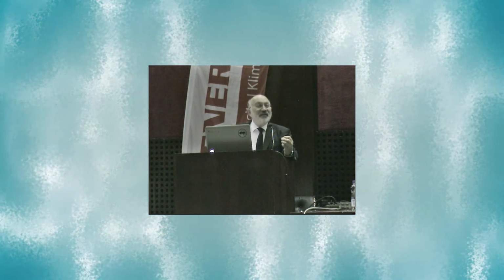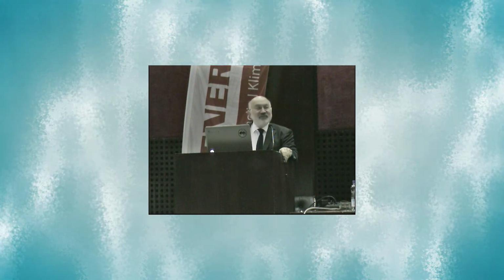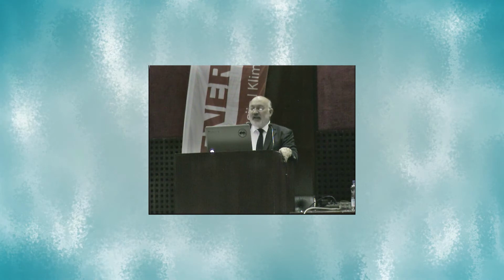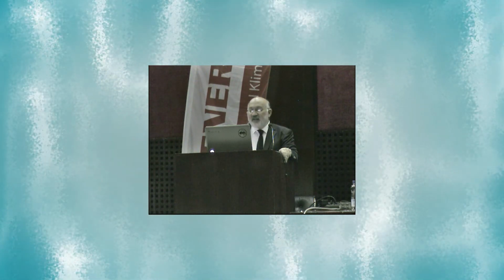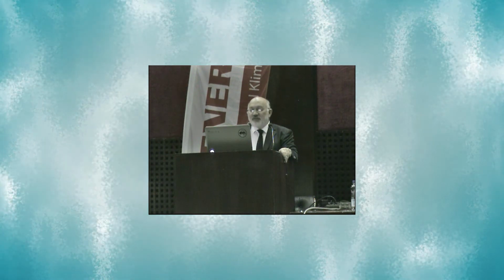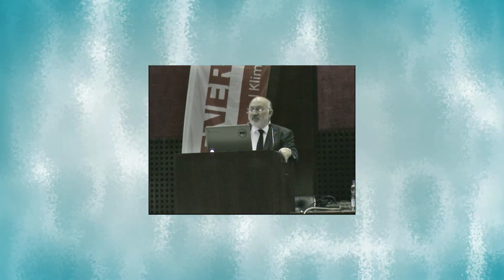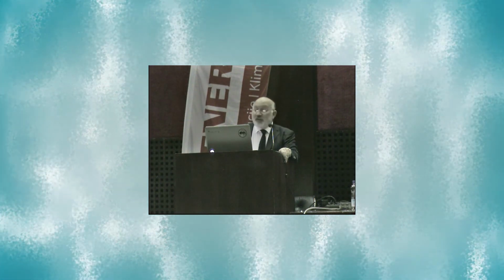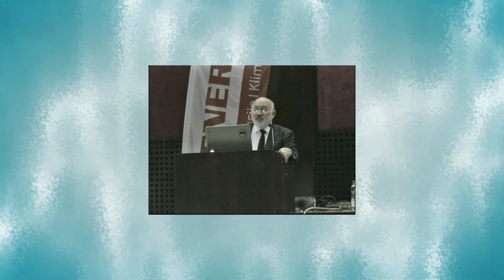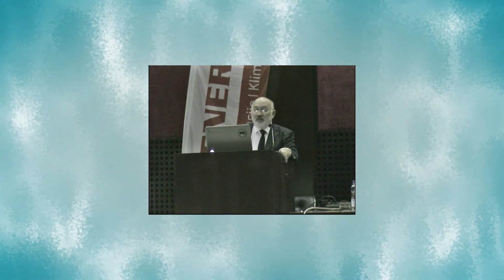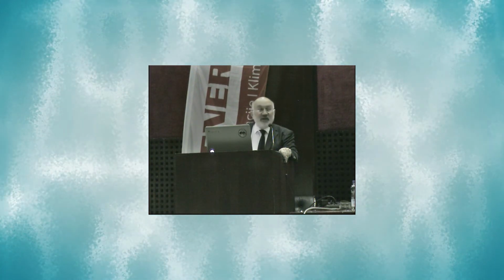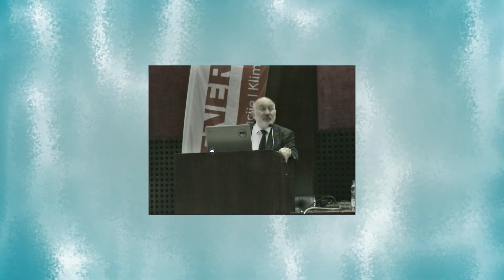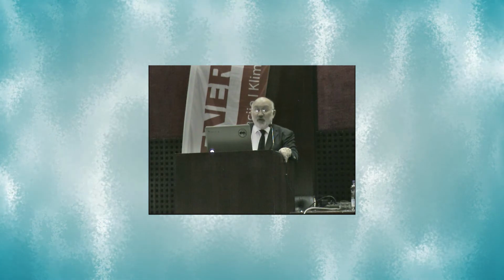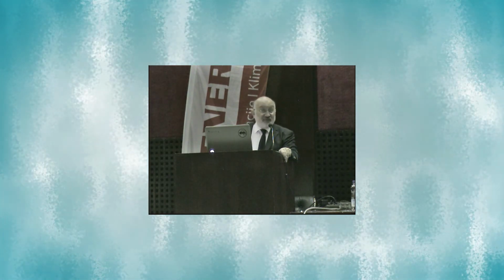Some results are shown here in a TS diagram, with R134A in blue and CO2 in green, for exactly the same conditions, shown by the dashed lines for air inlet and outlet from the condenser and evaporator. For CO2, the same size gas cooler or condenser brings the temperature much lower than the condensation temperature in the condenser. So instead of subcooling, we're able to bring the exit to a lower temperature than subcooling, and the contribution of the internal heat exchanger is much more significant.